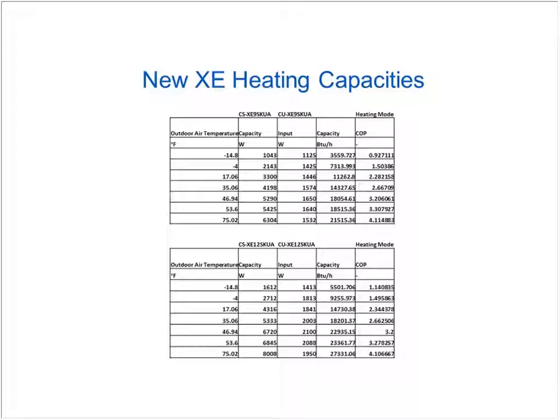At 75 degrees, I don't need much heat, but my COP is great. I live between 35 and 46 degrees, that's where I want to be. So in this case, it's a 2.6, 3.2. So when a manufacturer starts telling you how great their COPs are, the question is, COP at what point? I mean, anybody can do a good job at 75 degrees. The money in ductless heat pumps is at 35 to 46 degrees value.